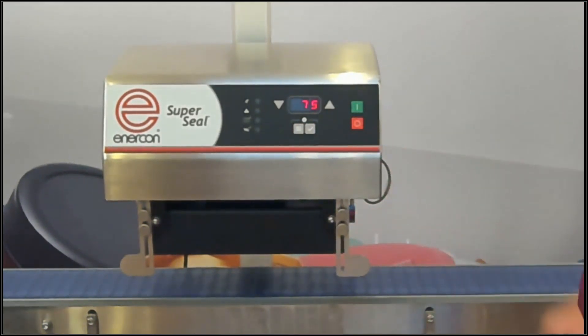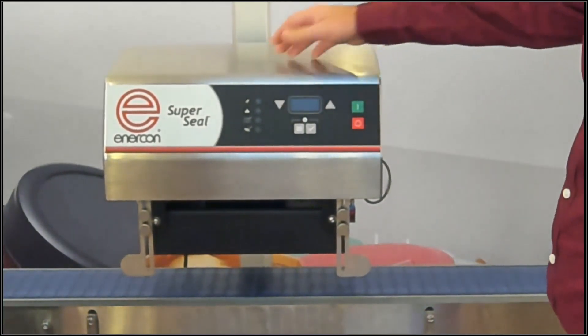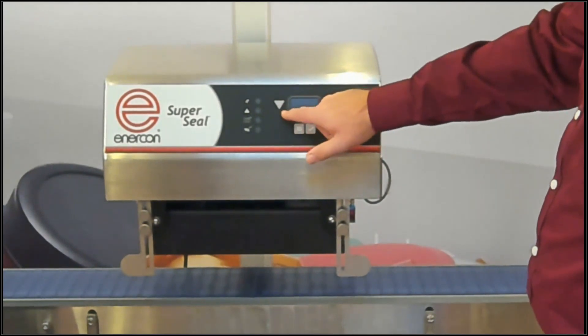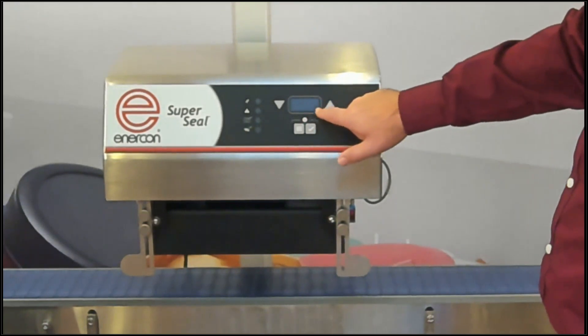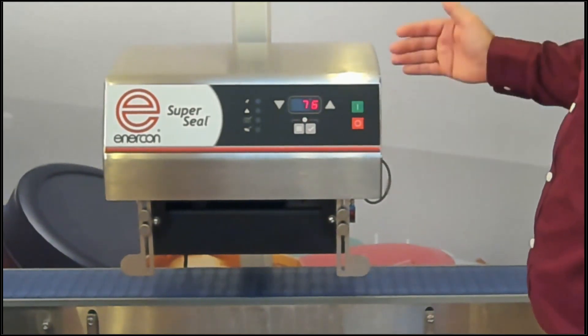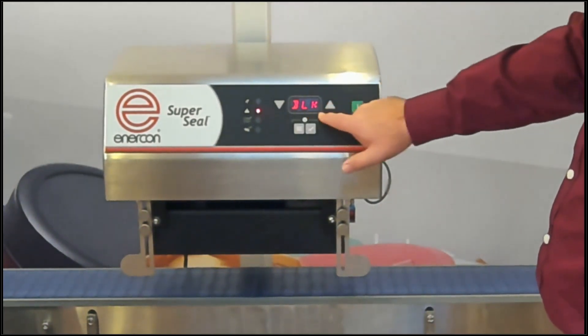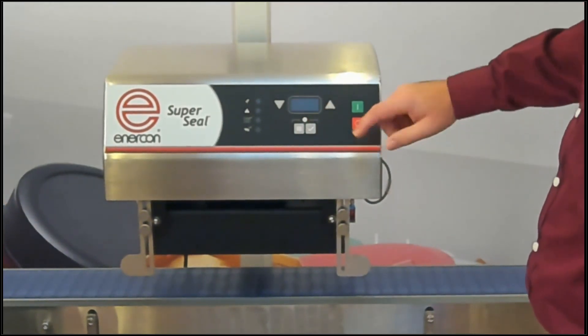One of the differences on the new SuperSeal is how faults are displayed. Previously, when there was a fault — a stalled bottle fault or an interlock fault — we'd have a cryptic code like F00 or F03, and you'd have to look at the manual to decode it. Now, if you block a sensor, instead of saying F06, it says 'block.' So the operator knows exactly what's going on, can clear the blockage, and reset the fault.